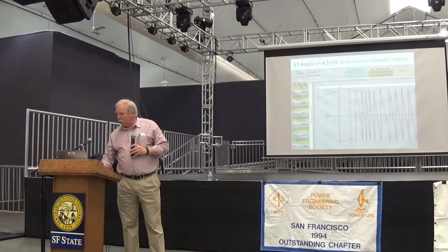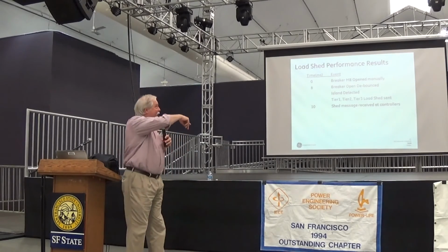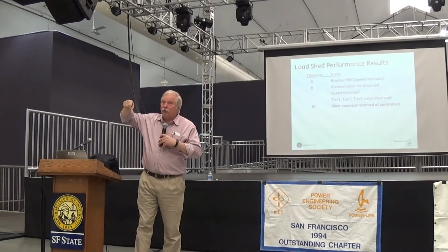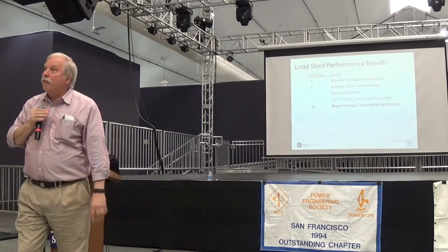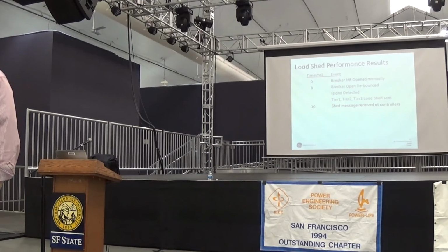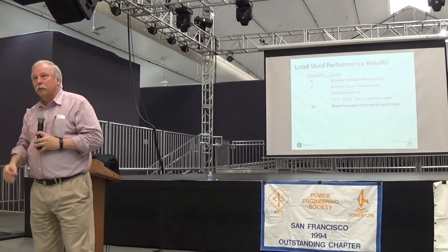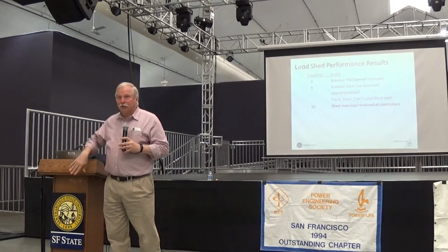If there's more interest, there's a whole paper on this. Bottom line is, in the test we ran, from initiation of the island at time 0 until the load shed message was received at all the remotes was 10 milliseconds. Of that 10 milliseconds, 8 milliseconds was debounce time on the digital input from the breaker auxiliary contacts in the yard. So the actual time to make the calculation was 2 milliseconds.